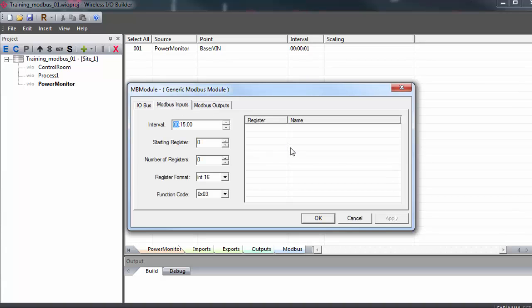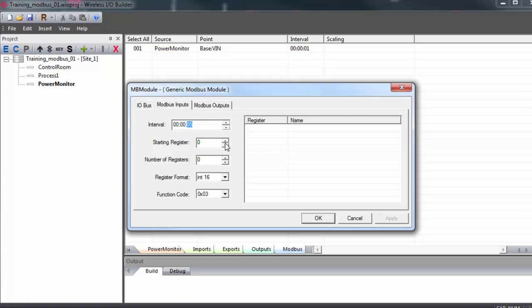So next, we'll go to the Modbus inputs. And these are the registers we will read from the slave. I'll set the interval down to 5 seconds. Again, the minimum possible is 1 second. Starting register, this corresponds to your slave device's database. Here we start counting from register 0. So if your slave device starts counting at 0, then they will match up. Otherwise, if your device starts counting from 1 or 40,001, you would have to keep that offset in mind.